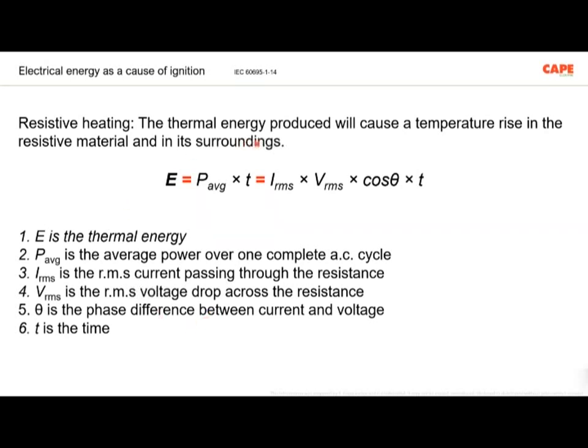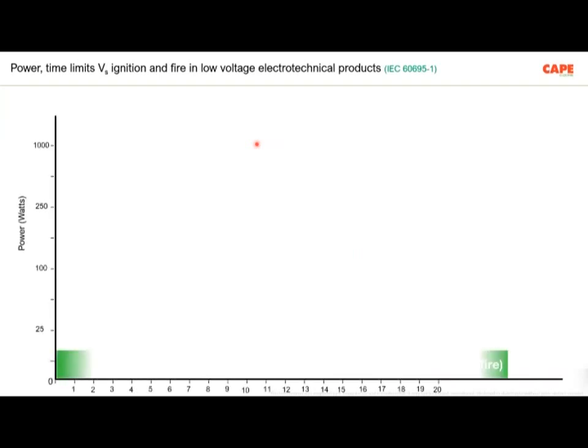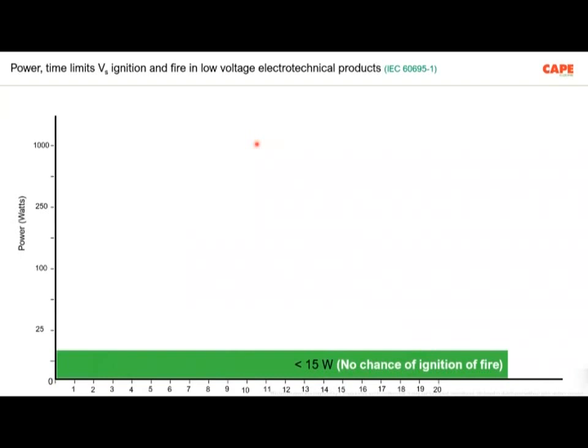I'm not going too deep because these are subjects which require a lot of attention. One simple concept which is followed is that any electrical apparatus consuming a power of less than 15 watts is not supposed to ignite fire. There is no chance of ignition of fire from an electrical apparatus consuming less than 15 watts. In the same way, for a device consuming less than 100 watts, ignition is possible only under certain conditions. The condition is if some ignitable things are nearby, probably the other items start burning.